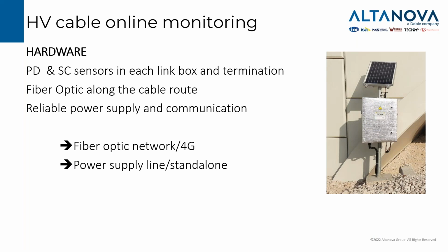A key point for permanent HV cable online monitoring is that we need a lot of hardware. For instance, we need a partial discharge and sheath current sensor in each link box. We need a fiber optic that runs along the cable route for communication. And we need a good and reliable power supply. In some cases, it is possible to bypass the problem by using standalone power supplies with solar panels or 4G communication instead of fiber optic, but this is a case of retrofit, so it's normally a last resort solution, and it's much more expensive than having a fiber optic on the cable and a power supply line.